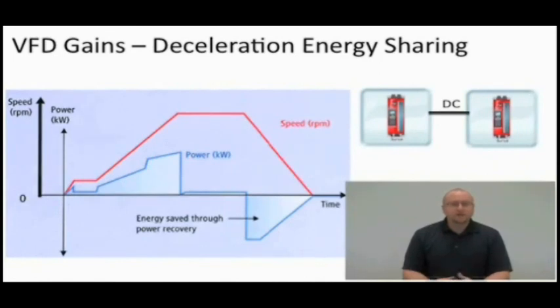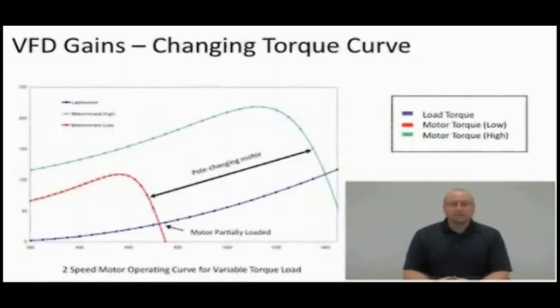So you can actually recover some energy losses if you couple the DC links together, or if you use a regenerative power supply. The way that those work is when your motor ramps down, it acts like a generator, pumps energy back into your variable frequency drive. That energy can be sent to a regenerative power supply, which conditions the energy and sends it back on the line. That way it's not wasted. A regenerative energy power supply is usually at a premium here in the United States. They're expensive, but if you look at the long-term goals and the long-term gains you can achieve with this, they are worth the money.